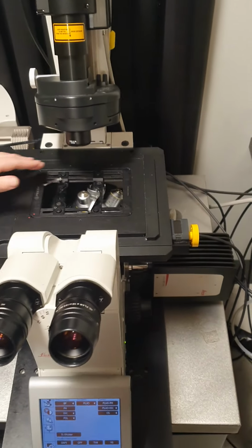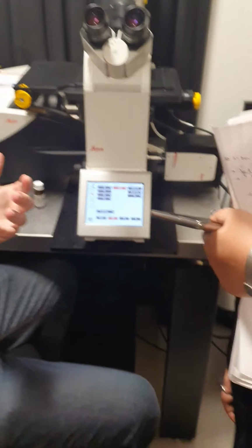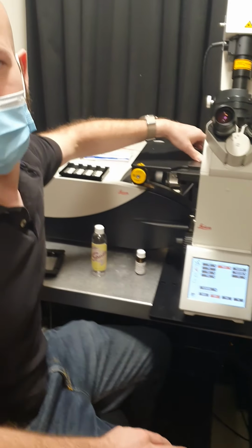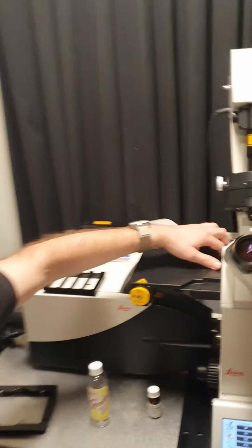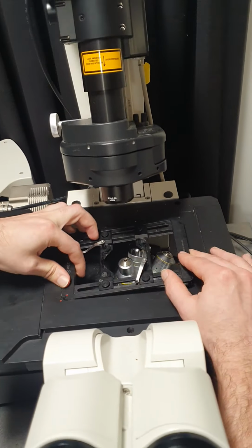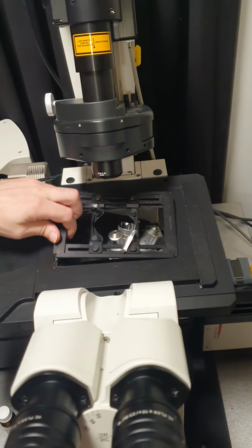Because sometimes when people get me and they're having problems, like, oh, my focus keeps drifting, it's because their specimen holder isn't in there properly. It's sort of like sitting like this and wobbling around.